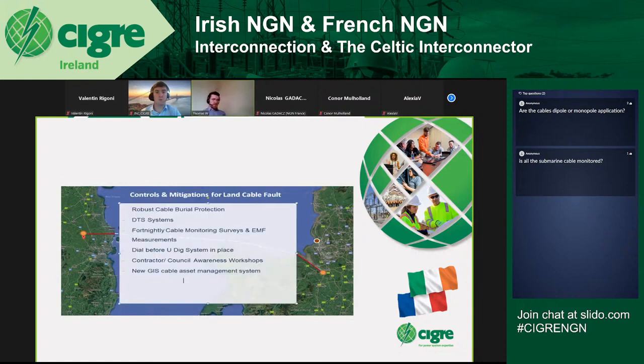The controls and mitigations we have in place for land cable faults include robust cable burial protection systems and distributed temperature sensing systems. We do fortnightly cable monitoring surveys in the form of a road drive and take EMF measurements. For contractors possibly working near the cable, we have dial-before-you-dig systems where contractors log any work near the cable and are given guidelines for working in the area.